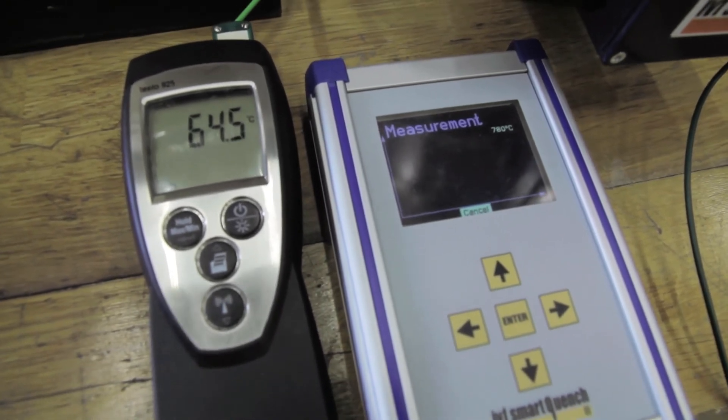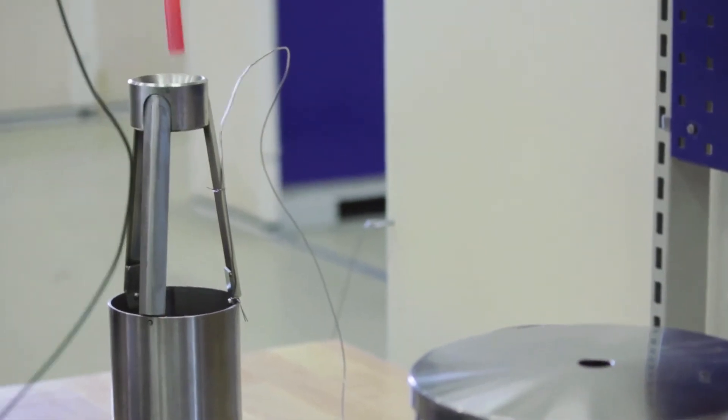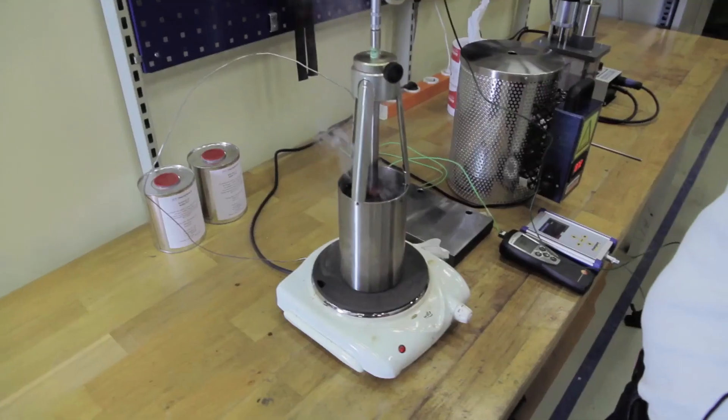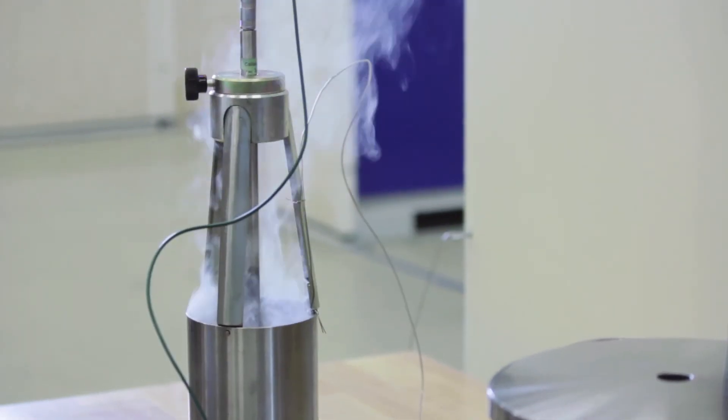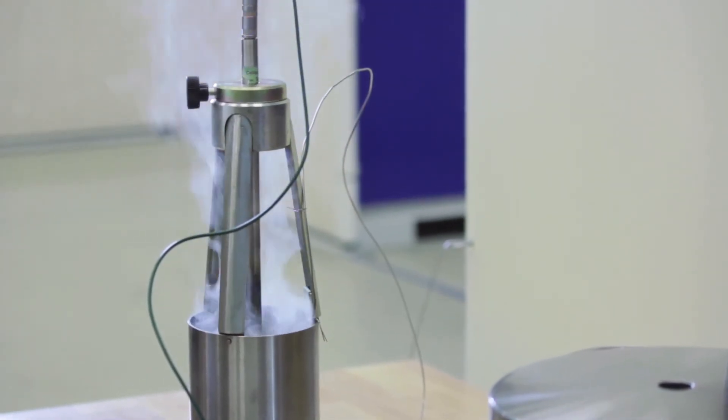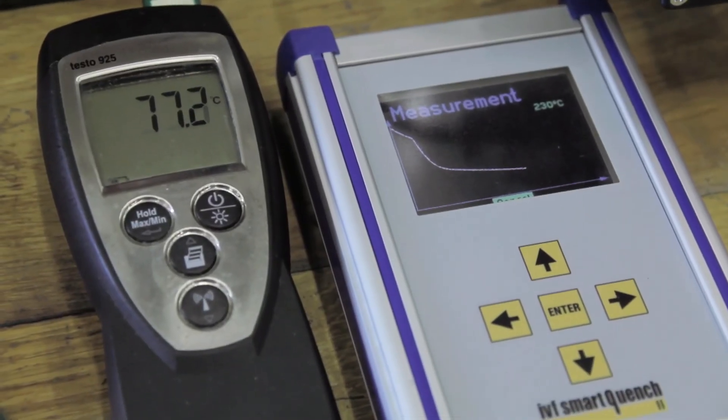As soon as the probe has reached the correct start temperature, rapidly lift the probe straight up, move it to above the quenchant, immerse it and let the cone find its place in the tripod. After the probe is positioned in the tripod, take a step back and watch the curve that slowly appears on the display.